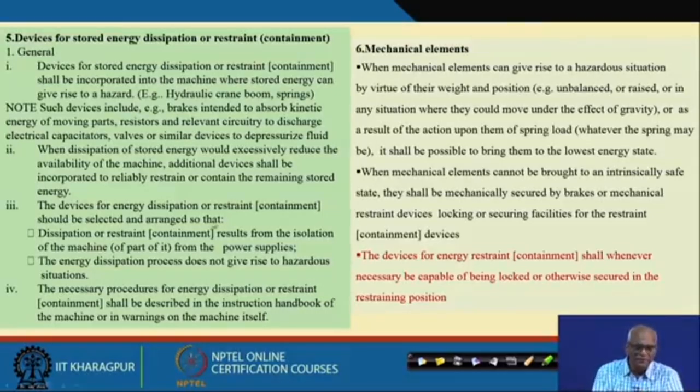The devices for energy dissipation or restraint should be selected and arranged so that dissipation results from the isolation of the machine, and the energy dissipation process does not give rise to a hazard. While dissipating the energy, you should not be trapped in a hazard. Suppose you want to release a spring, you should very carefully, through a procedure, dissipate it. So energy dissipation procedures should also be there.